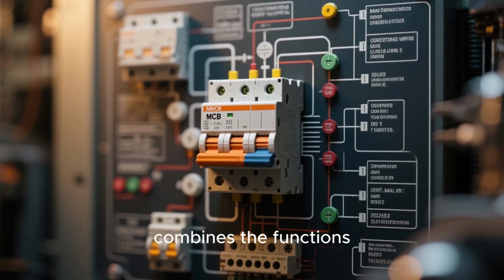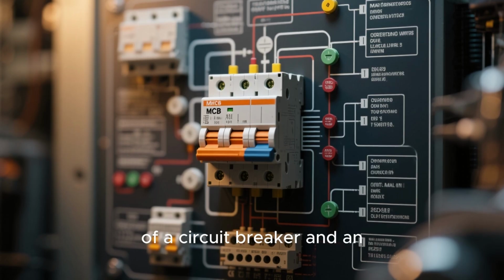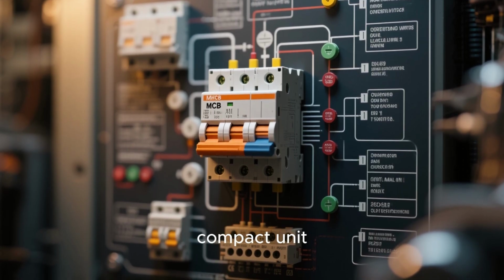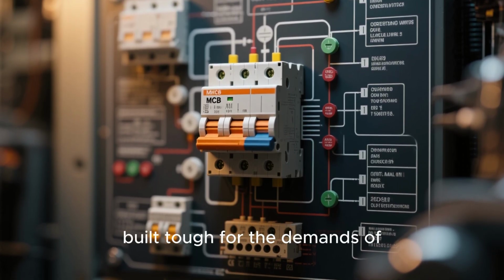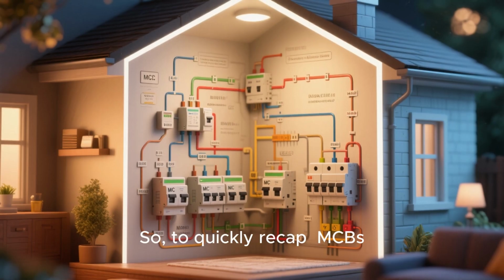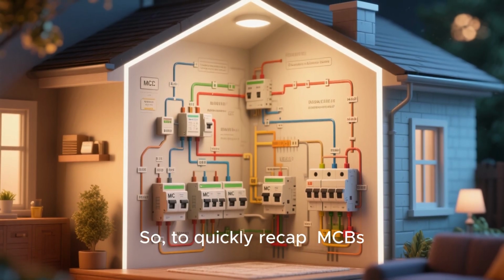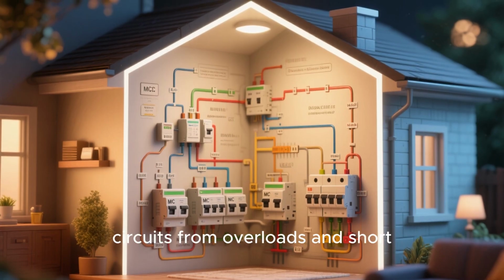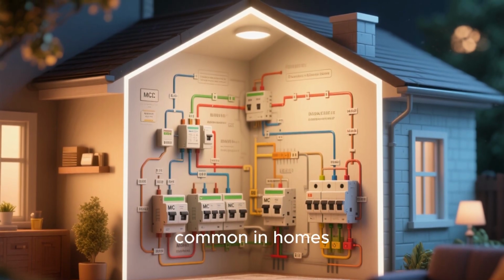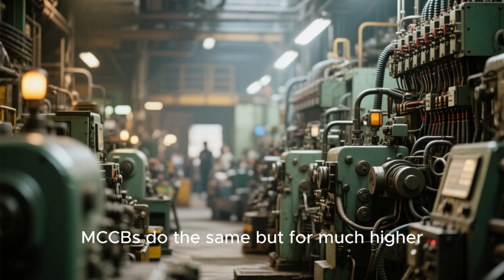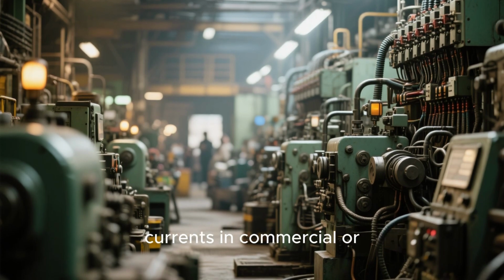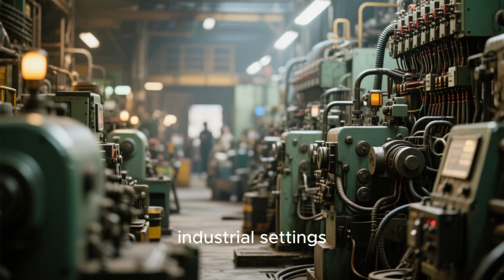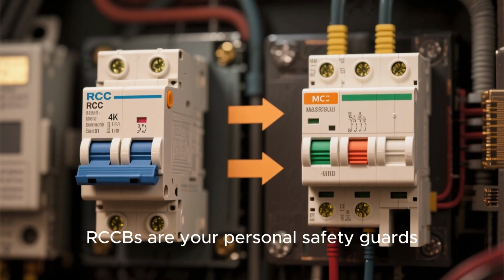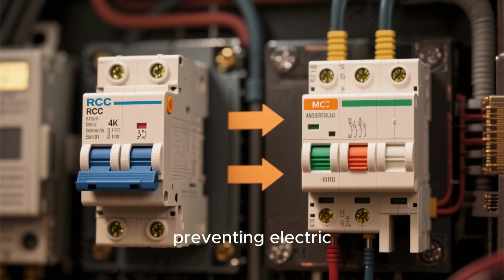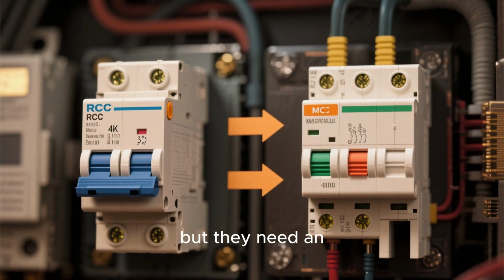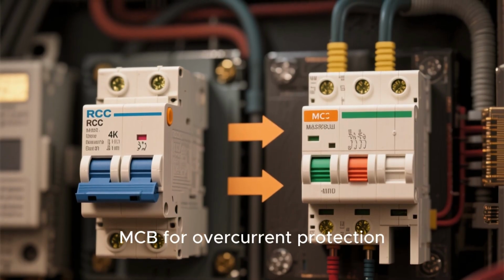It essentially combines the functions of a circuit breaker and an overload relay into one compact unit, built tough for the demands of industrial machinery. So, to quickly recap, MCBs protect individual circuits from overloads and short circuits, common in homes. MCCBs do the same but for much higher currents in commercial or industrial settings. RCCBs are your personal safety guards, preventing electric shock from earth faults. But they need an MCB for overcurrent protection.